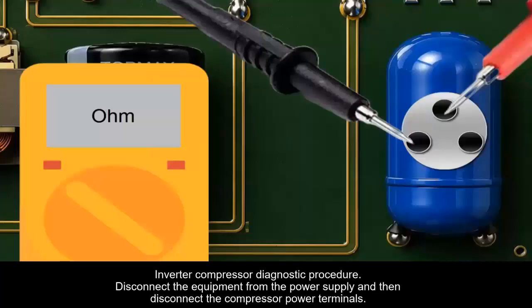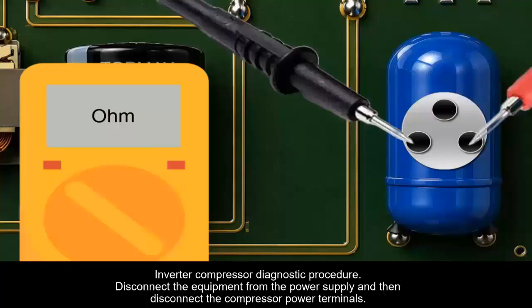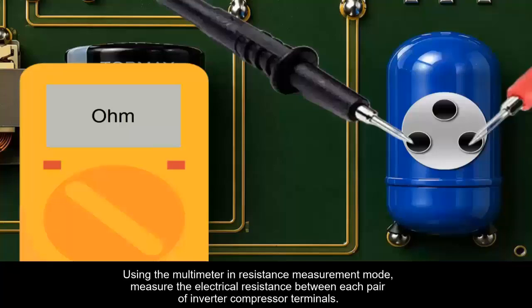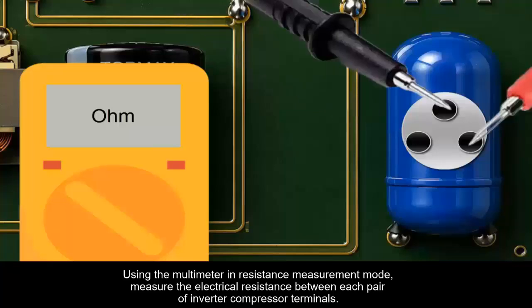Using the multimeter in resistance measurement mode, measure the electrical resistance between each pair of inverter compressor terminals. Correct reading: the resistance values obtained between each pair of terminals should be virtually identical. In addition, the measurements should never indicate 0 ohms or infinite resistance. These conditions may indicate an internal short circuit or open winding in the inverter compressor.